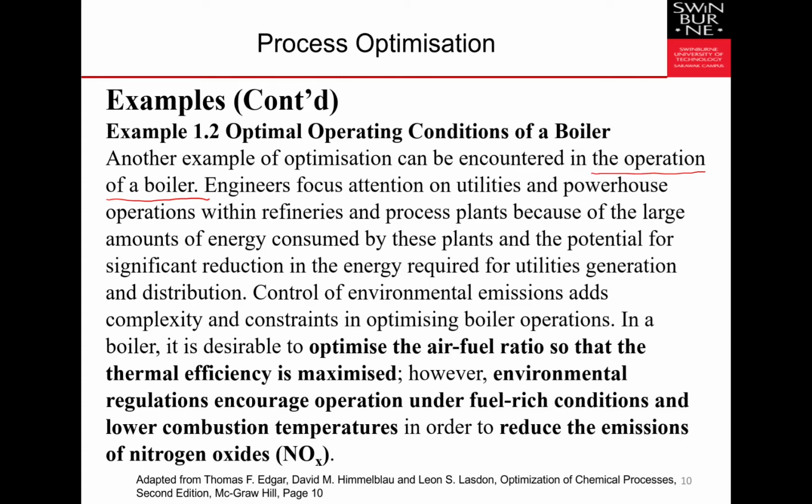Okay, the control of environmental emission these days has become an additional variable that process engineers need to take into consideration in optimizing boiler operation. So in a boiler, it is desirable to optimize the air to fuel ratio so that the thermal efficiency is maximized. However, there is an opposing consideration. Environmental regulation encourages operation under fuel-rich condition and lower combustion temperatures in order to reduce the emission of nitrogen oxides.